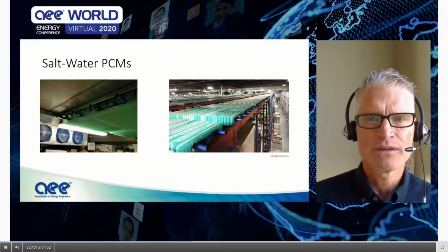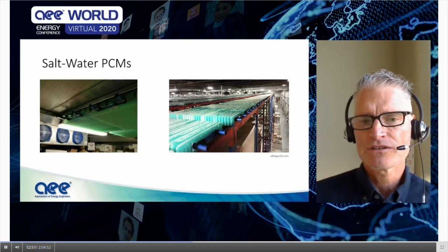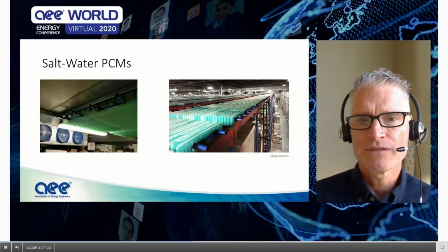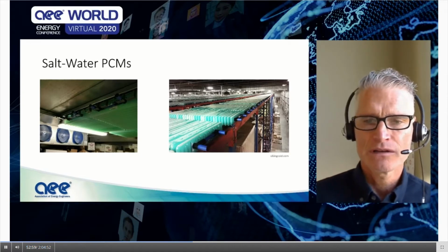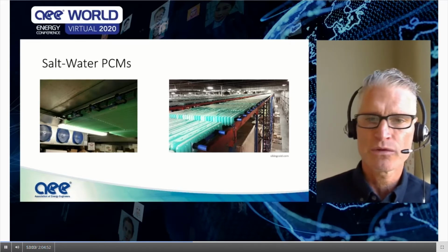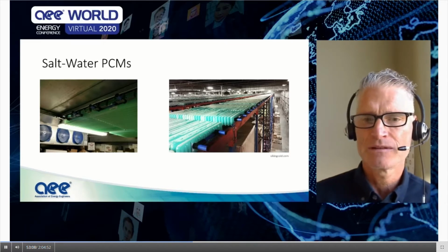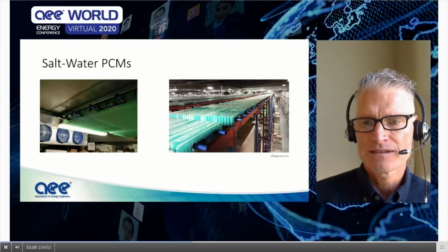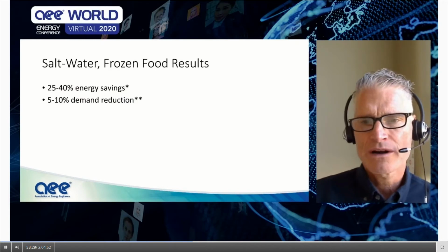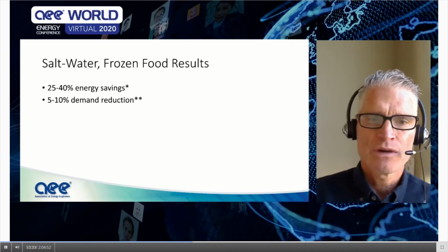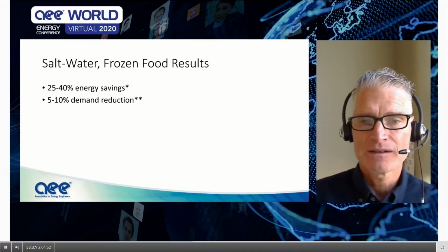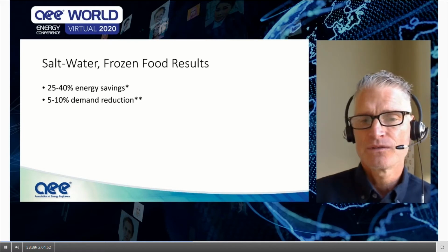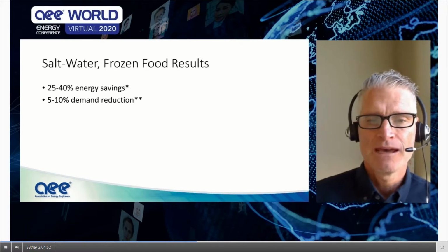The other thing is it allows the equipment to run at a fuller load. So commercial industrial refrigeration, or at least industrial refrigeration, runs more efficiently when it's more fully loaded, whether the compressors have part loading due to cylinder unloading for reciprocating compressors, or rotor shortening for screw compressors, or even variable frequency drives. The equipment and the systems run more efficiently when it's more fully loaded. And so, of course, we're shifting load from on peak to off peak, and we're saving energy at the same time, and so that results in a lot of dollar savings. So the tests that I looked at for salt water PCMs for frozen food were about 25 to 40% energy savings, which is a lot. Again, it's due to shifting to cooler periods, which allows reduced head pressure and running at full capacity.